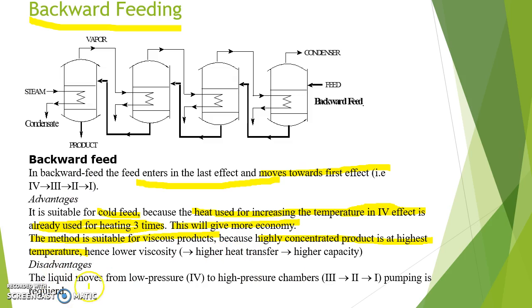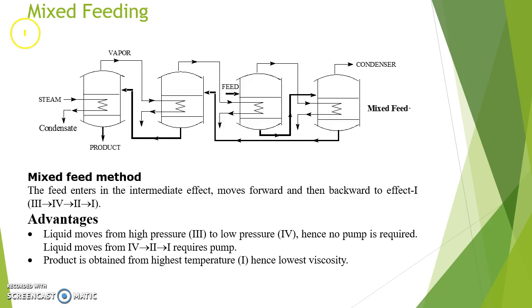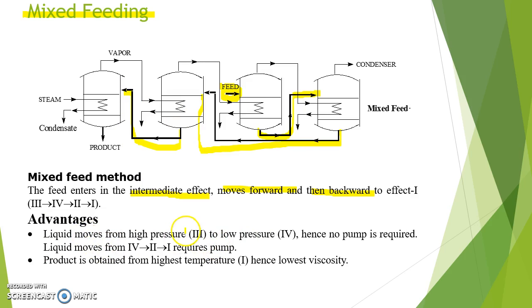The disadvantage of backward feeding is that liquid moves from low pressure to high pressure chambers, so pumping is required. In mixed feeding, the feed enters an intermediate effect, moves forward, and then backward to effect 1. In this diagram, feed enters the third effect, moves to the fourth effect, then from fourth to second, and second to first. The advantage is that liquid moves from high pressure to low pressure (third to fourth), so no pumping is required for that portion, though pumping is required from fourth to second to first. The product is obtained from the first effect at the highest temperature, hence lowest viscosity.